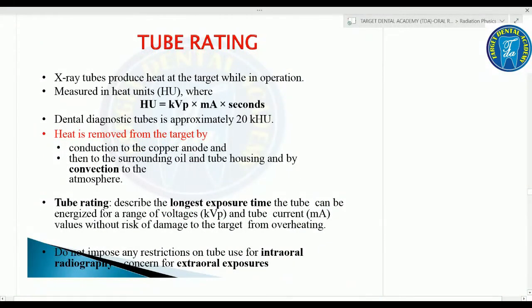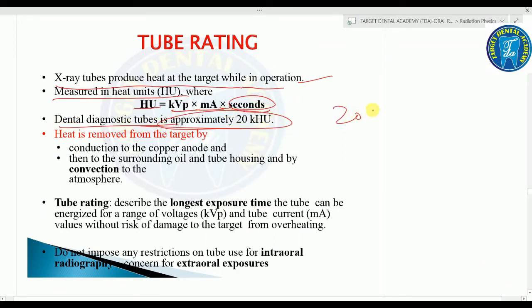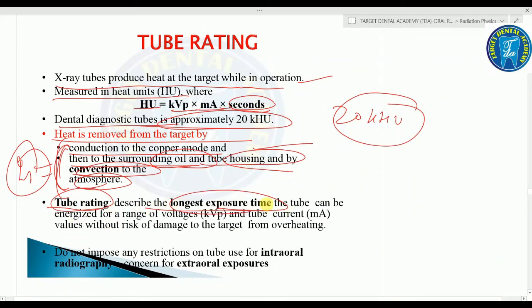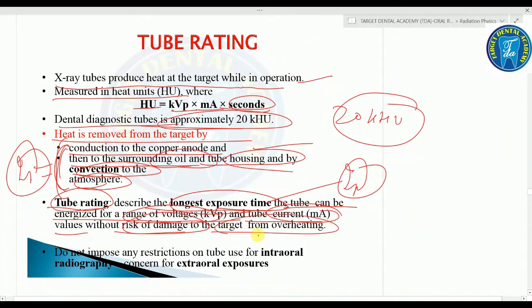Tube rating: X-ray tubes produce heat at the target during operation. Heat is measured in heat units (HU) = kVp × mA × seconds. The dental diagnostic tube is approximately 20 kHU. Heat is removed from the target by conduction through the copper anode, then to surrounding oil and tube housing by convection to the atmosphere. Tube rating describes the longest exposure time the tube can be energized for a range of voltages and mA values without risk of damage to the target from overheating.